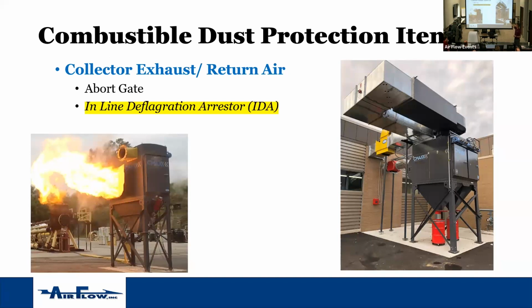Otherwise, you see like the one picture here, they didn't have the distance from the spark sensor, which was located right, actually there's a spark sensor right there. They needed to get that distance from here over, so they actually had to create this U to come in. If this stuff would have been larger, based on the calculation, we might have been able to get rid of some of this and go straight in. But it's all based on that feet per minute through that system.